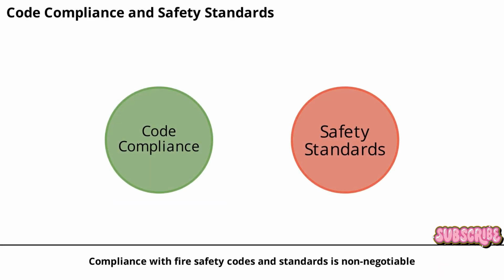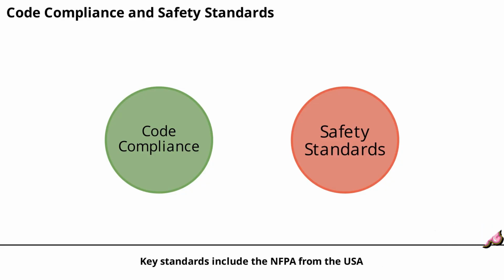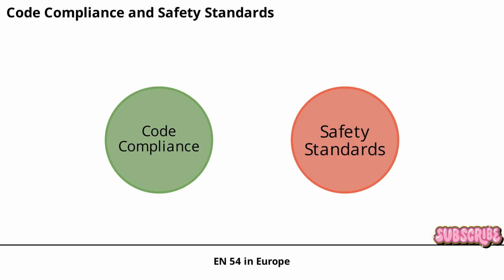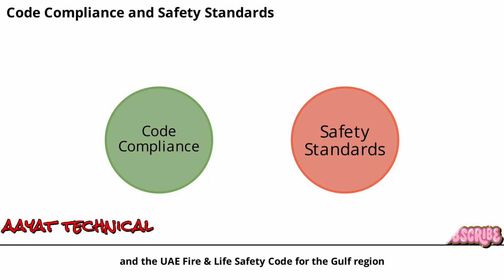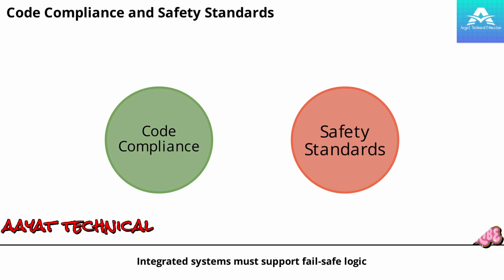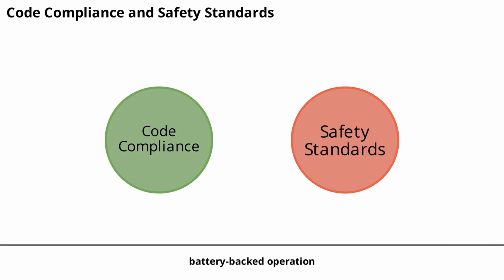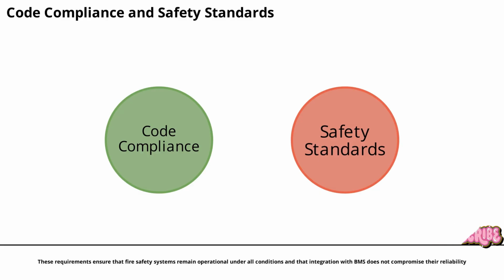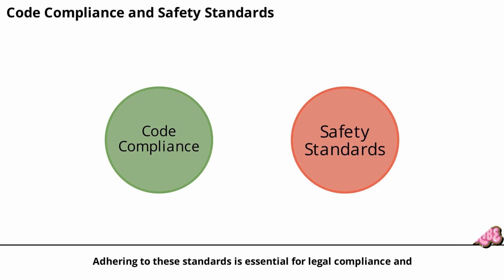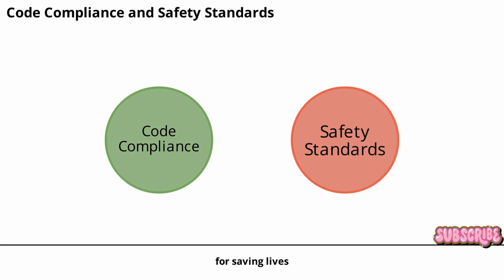Compliance with fire safety codes and standards is non-negotiable. Key standards include the NFPA from the USA, EN54 in Europe, and the UAE Fire Life Safety Code for the Gulf region. Integrated systems must support fail-safe logic, battery-backed operation, and periodic testing with acknowledgement. These requirements ensure that fire safety systems remain operational under all conditions and that integration with BMS does not compromise their reliability. Adhering to these standards is essential for legal compliance and, more importantly, for saving lives.